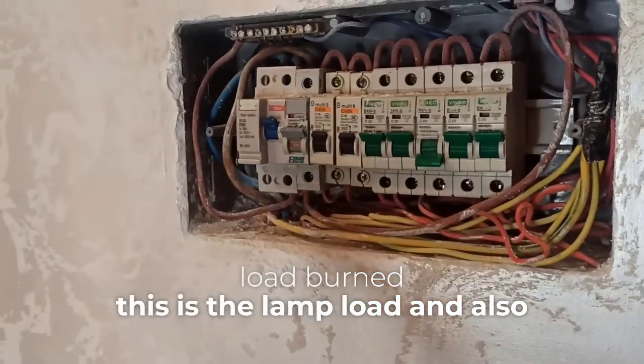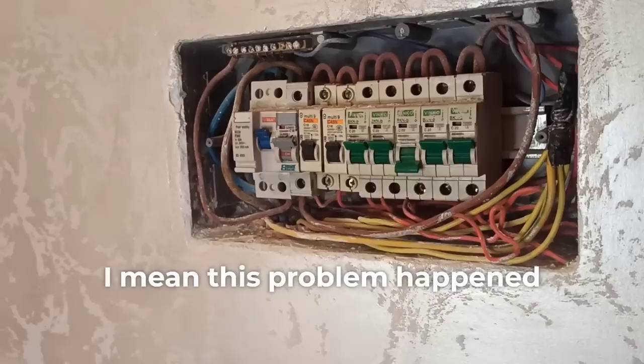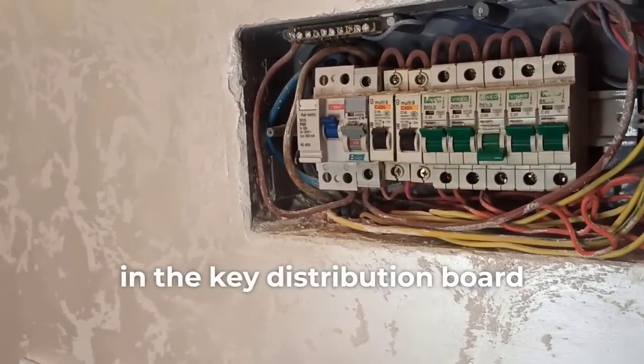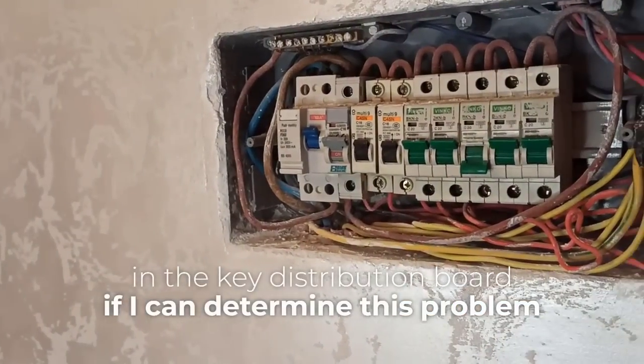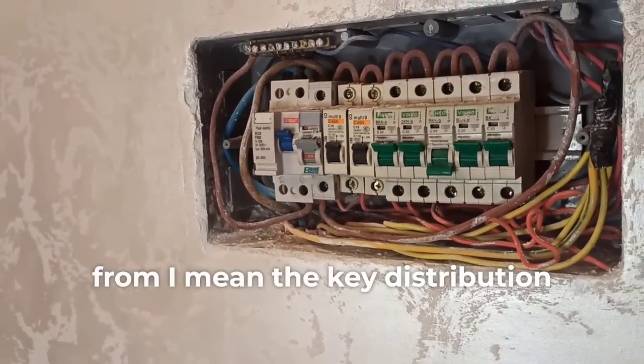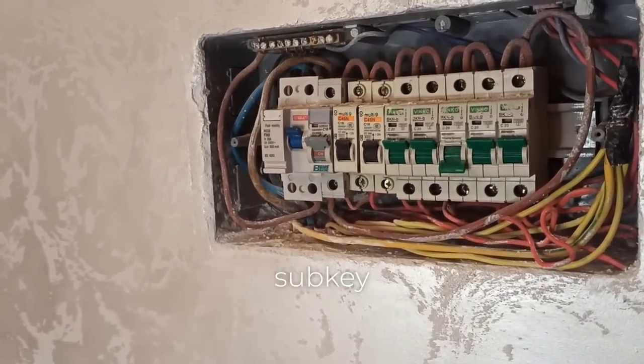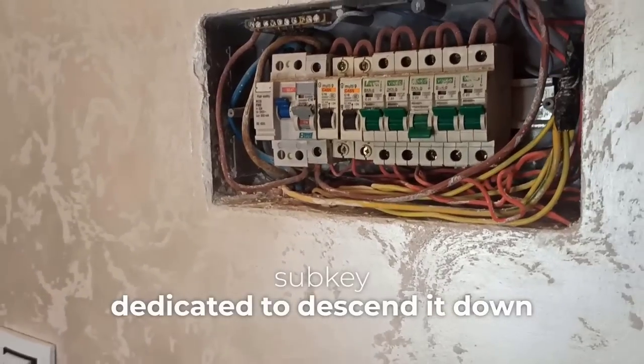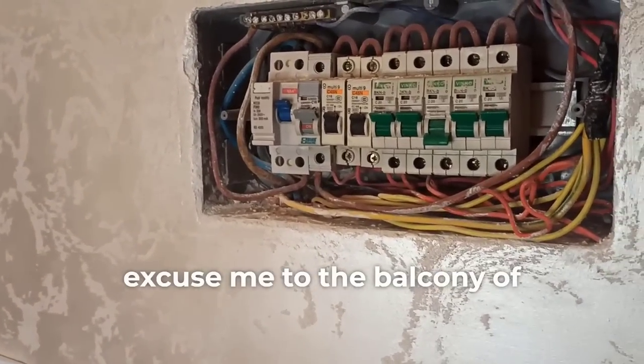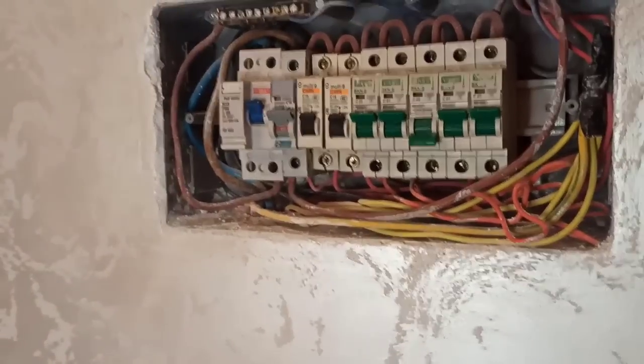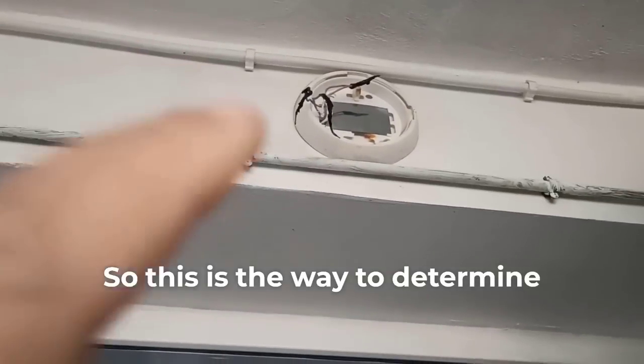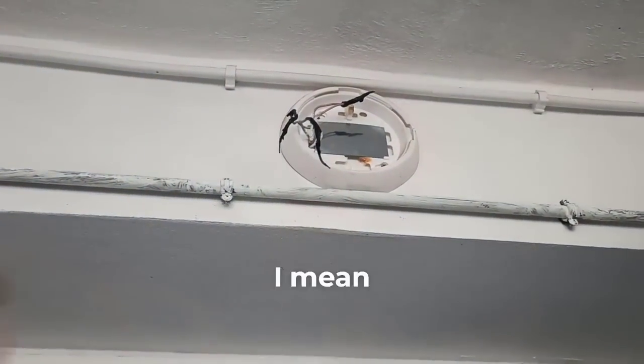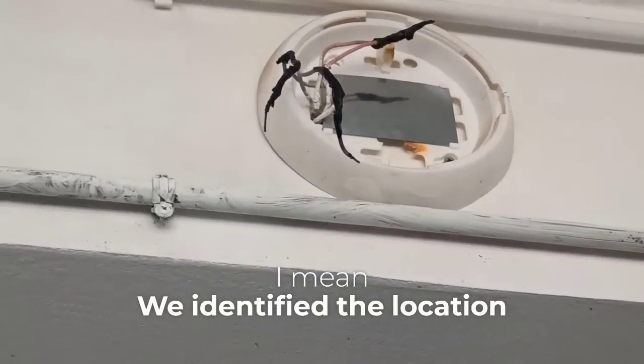This is the lamp load, and also this problem happened to me in the distribution board. I can determine this problem from the distribution board when I knock down this sub-breaker dedicated to the balcony of the house. So this is the way to determine the electrical circuit location. We identified the location of this problem, in the balcony of the house.